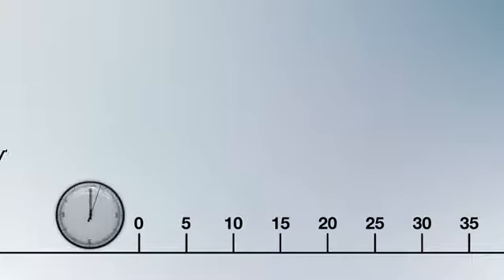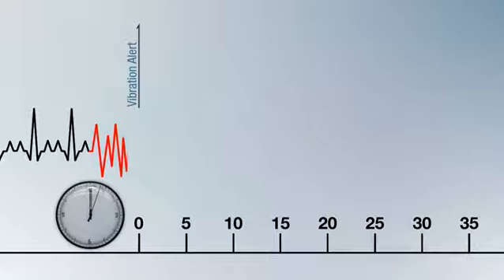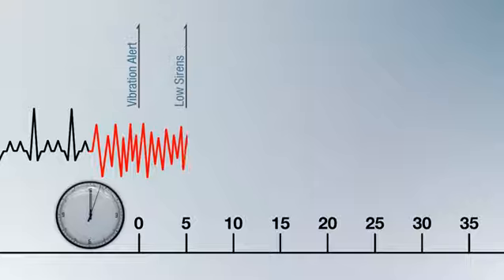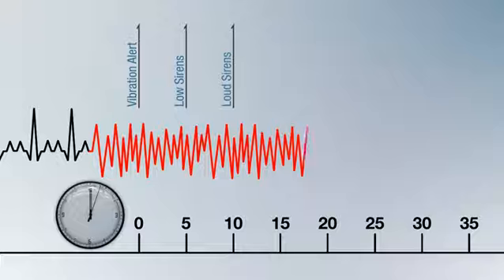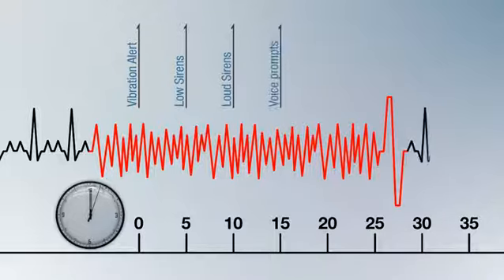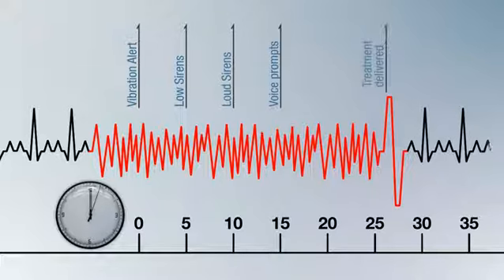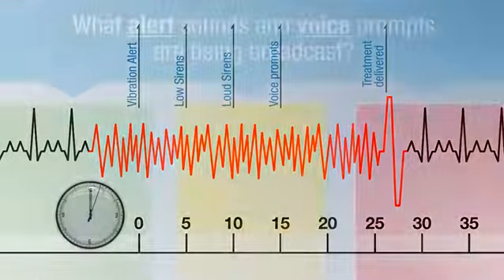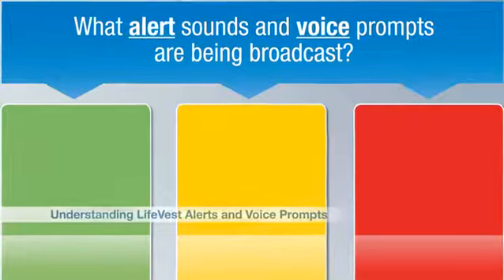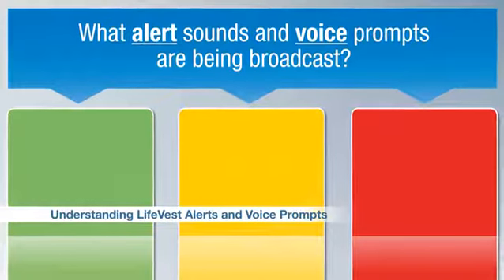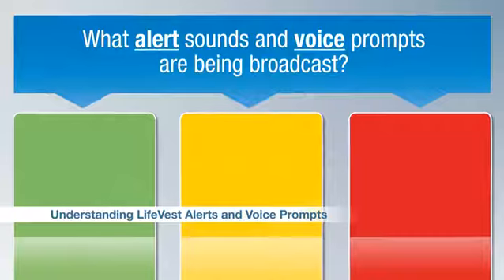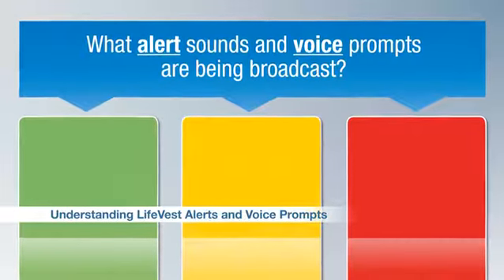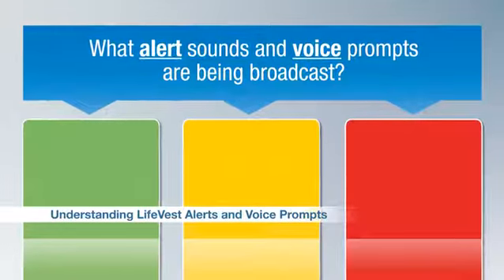If, however, the patient is unconscious, the sequence will run through a 5-second vibration alert, followed by a low, single-tone siren, which is broadcast for 5 seconds, followed by 5 seconds of loud, 2-tone sirens. The device then transitions to voice prompts accompanying the 2-tone siren. In order to quickly and effectively care for a patient wearing the LifeVest, it is important to understand the different alerts and voice prompts that may be broadcast from the device.